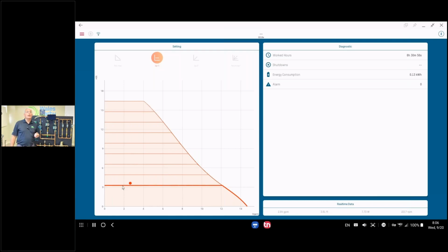So Chris, if you could now click on that 3-foot line or a little lower, if possible, just with the mouse. Or in fact, go up. I'm sorry, go up. We're probably at the lowest we can go. Go up to where it says 6 feet of head. Right there, please. Thank you. So what I'm doing here is we're actually dialing in where we want it to be. So I can change that. Were you able to do that, Chris? Well, if I did change that, you would immediately hear the circulator change its speed, and we could dial in whatever GPM and head that we want.